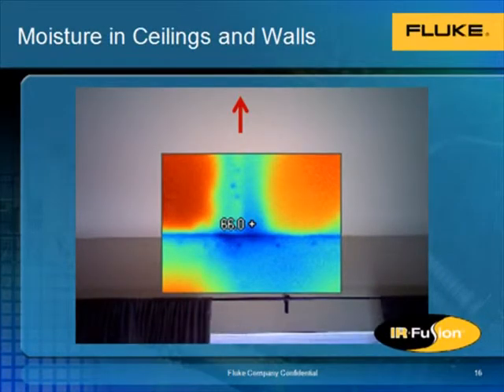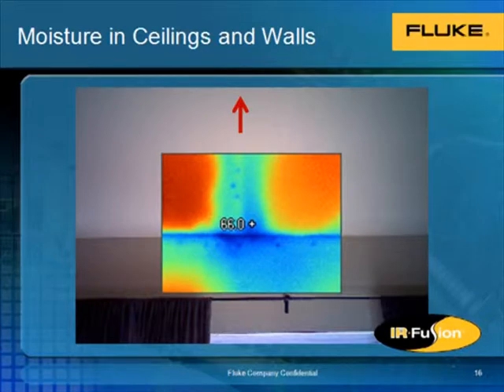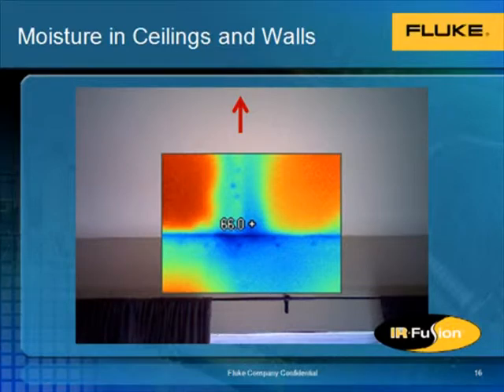Here is another example of moisture in ceilings. The source of the leak is actually up above where the red arrow is pointing. Because this is a vaulted ceiling, the leak is far up above and the moisture and water is actually running down the slope and pooling once it meets the wall. The Fluke IR Fusion is very helpful here because it helps pinpoint where along this wall the moisture is pooling. Without that visual reference image, it would be very hard to tell where that's actually happening.